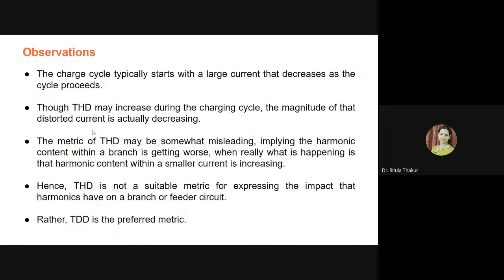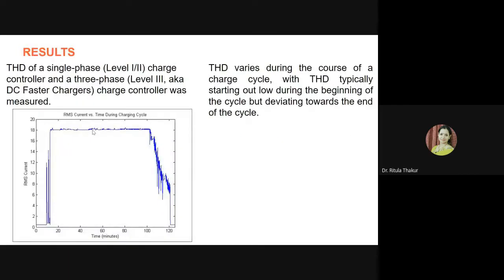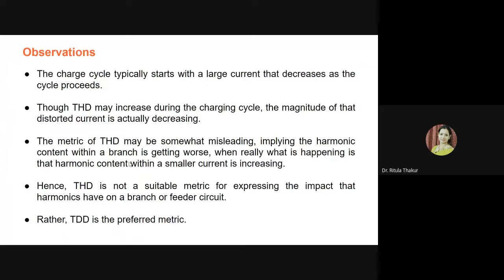Now what happens is that initially at the beginning of the cycle, it is low. As you can see from here also, in the beginning of the cycle, the THD is comparatively low, but towards the end of the cycle, there is a lot of deviation. So we can say that the charge cycle typically starts with a large current that decreases as the cycle proceeds. Although THD may increase during the charging cycle, the magnitude of the distorting current is actually decreasing. So we may say that the metric of THD may be somewhat misleading, because it seems the harmonic content is getting worse, but actually what is happening is that the harmonic content within the smaller current is increasing.